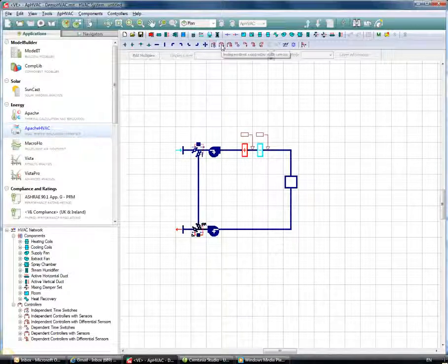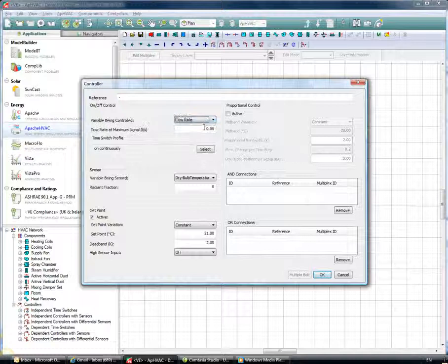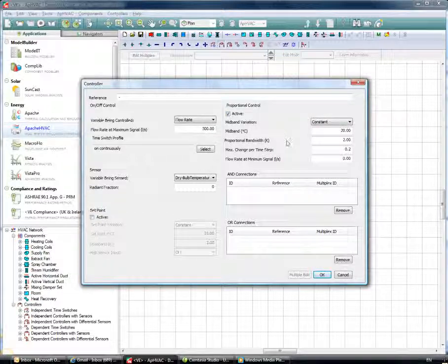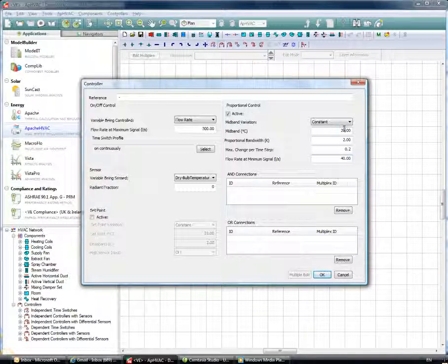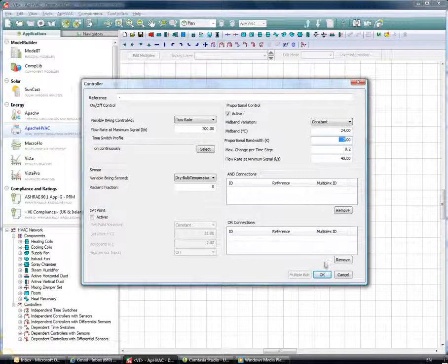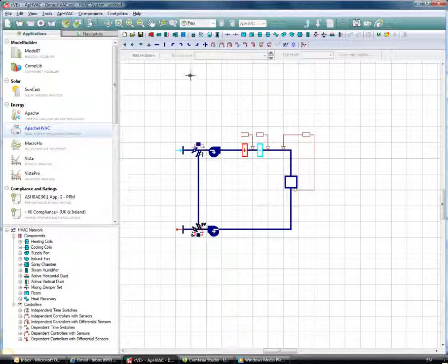The next controller is a flow rate controller — an independent controller with sensor. I'll position it sensing the air outside the room and controlling the flow rate to 300 liters per second with proportional control, which allows us to vary the flow rate in line with sensed temperature. The minimum will be 40 liters per second. The sensed variable is dry bulb temperature with a setpoint of 24°C and a proportional bandwidth of 2. I'll name this 'Flow Rate Control' and click OK.